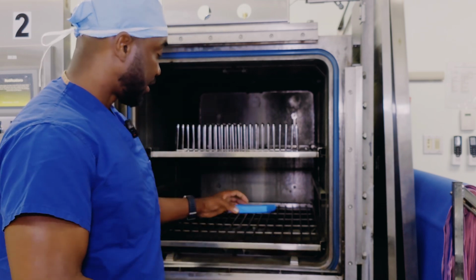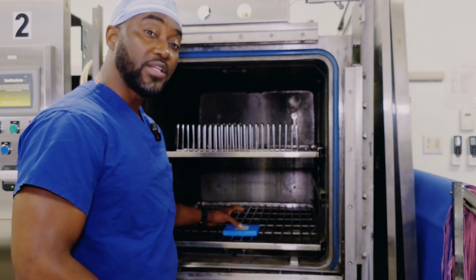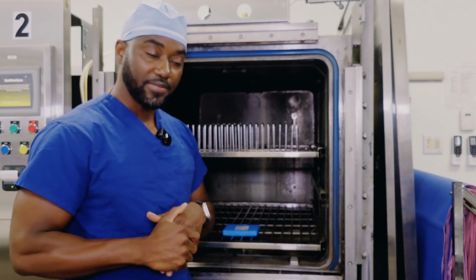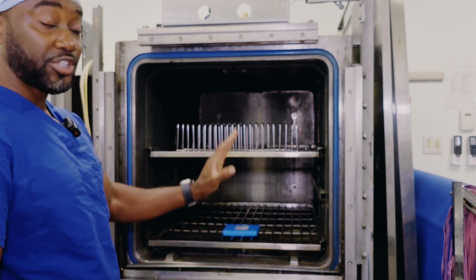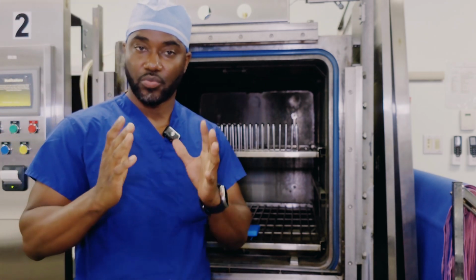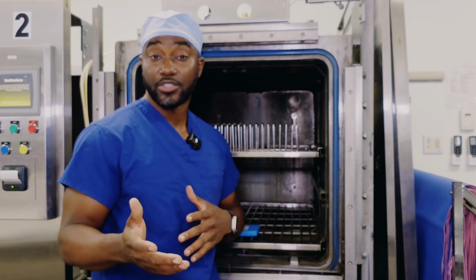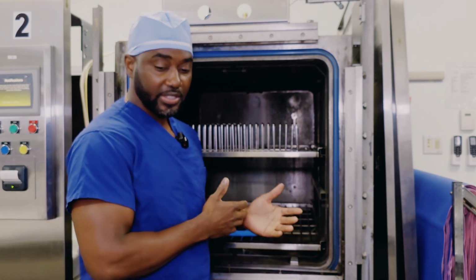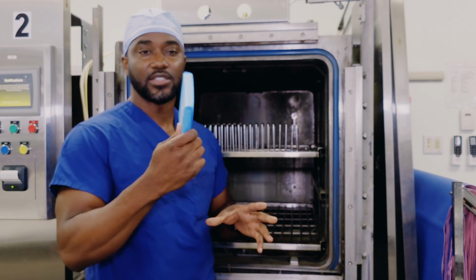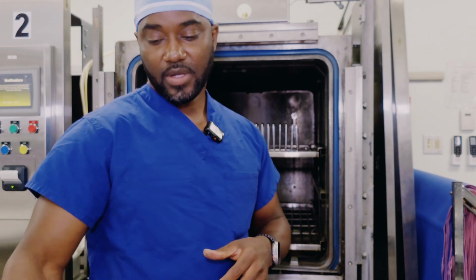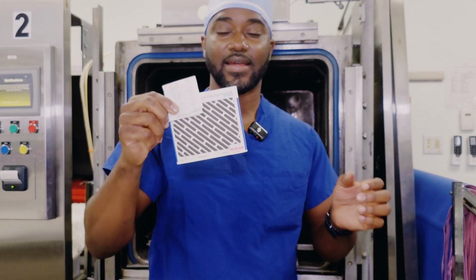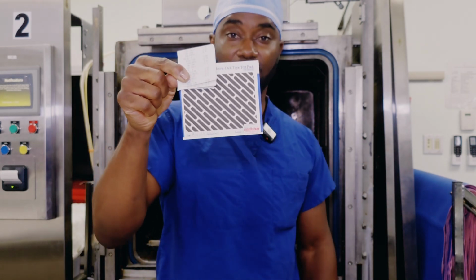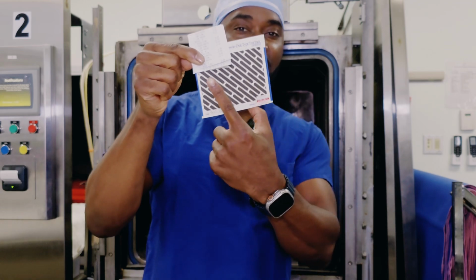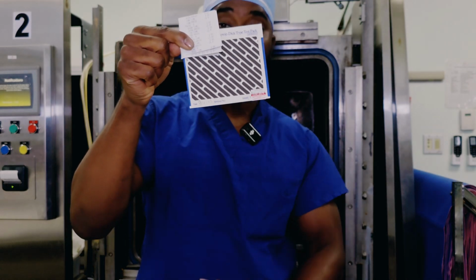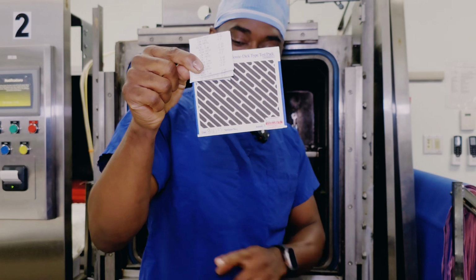You insert this Bowie-Dick test packet right over your drain strainer, where air escapes the autoclave. This autoclave door is now shut and a Bowie-Dick test is run. Depending on the manufacturer's instructions, you go by the parameters on the Bowie-Dick test. After this test is run, you have to open it up. A passing Bowie-Dick test result, which indicates that there has been a total escape of air from the autoclave, will look like an even black coloration across the sheet that comes out of this packet.